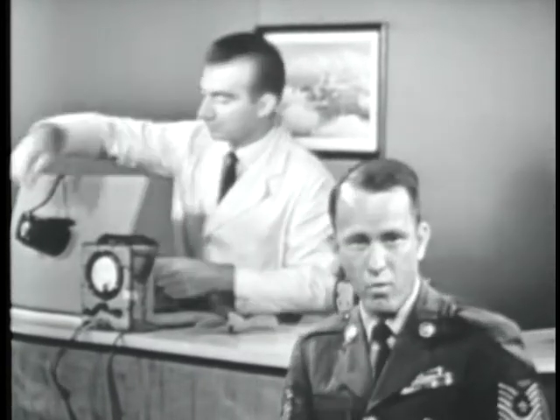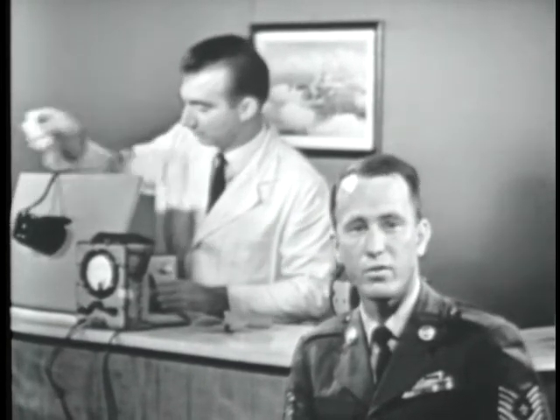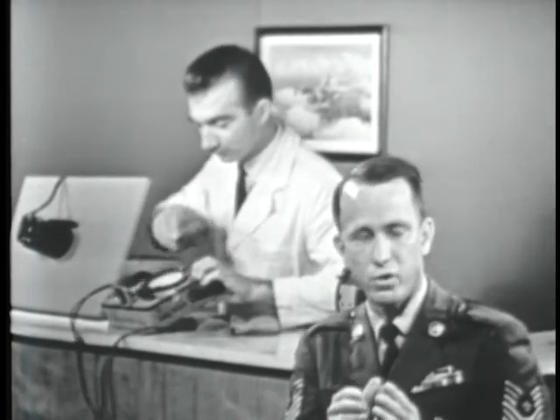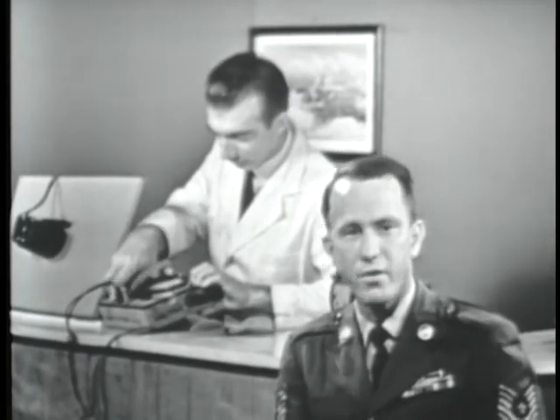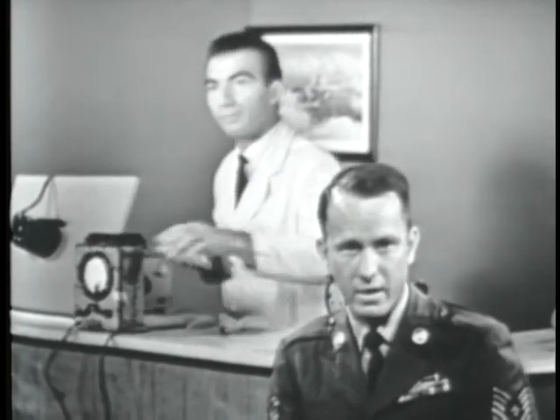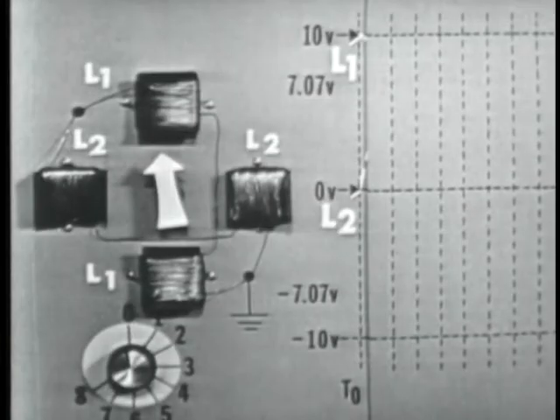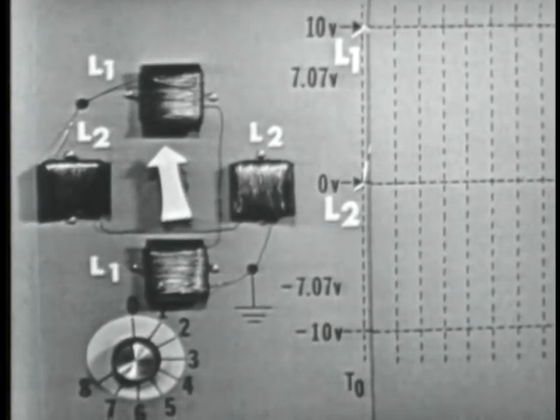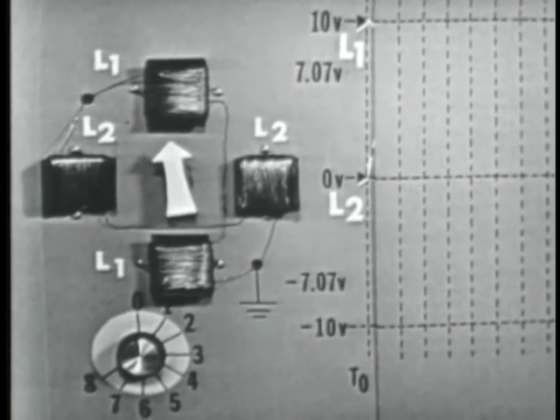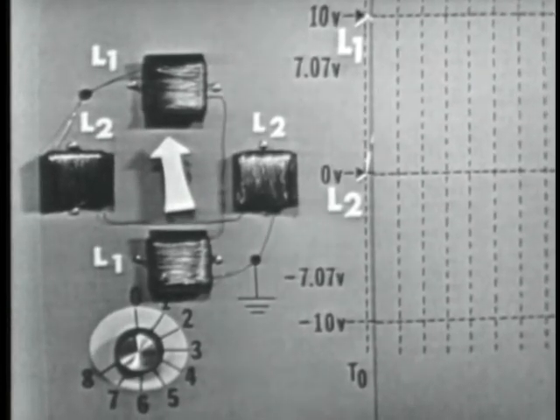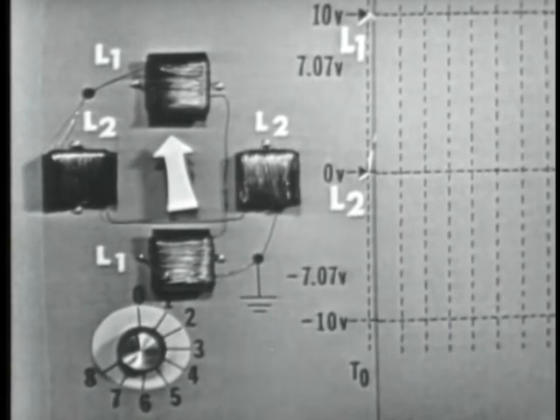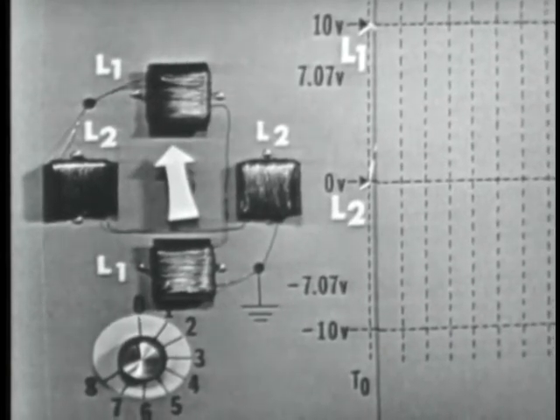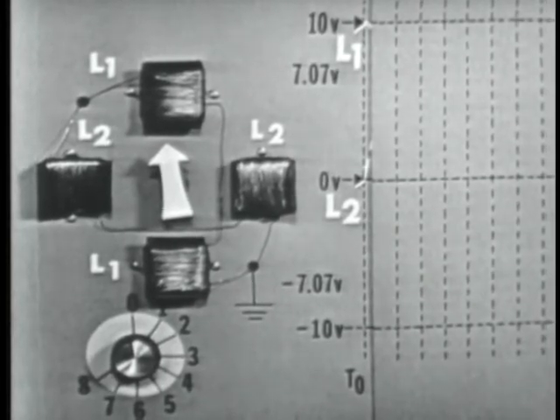There are two major points to understand about how the induction motor operates. First, we must have a rotating magnetic field produced by the stator windings. Second, we must cause the rotor to become an electromagnet. These four coils represent the stator windings of the induction motor — made from a deflection yoke from an old television set. The stator windings in the induction motor are not made exactly like this, but the magnetic field produced is essentially the same.